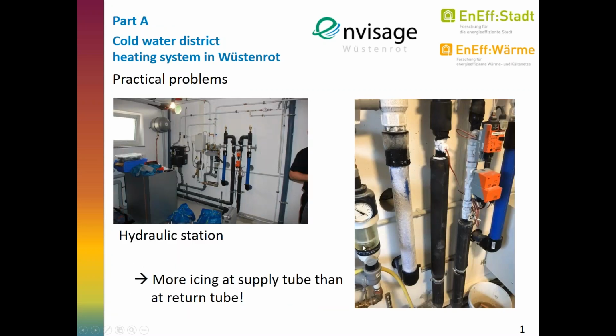We also faced some problems, but this was a quite interesting one. We have this cold district heating network — here's the supply line from the network, and this is the return from the heat pumps to the network. What you can see here is some icing on the supply line, which was confusing, because normally this shouldn't be iced, but this one should be. It was in the early stage of operation, so there was no insulation yet and we could see it.